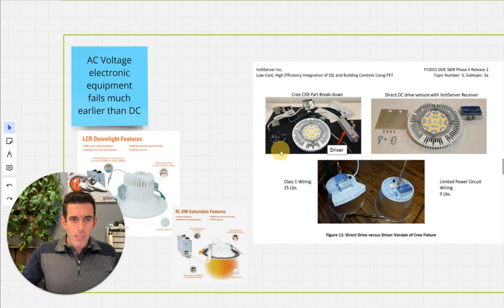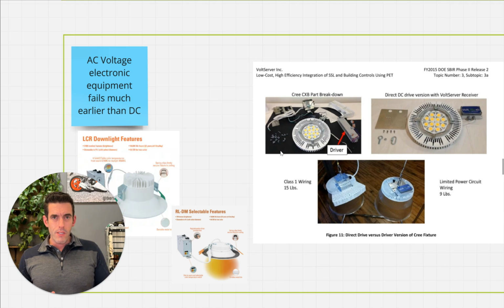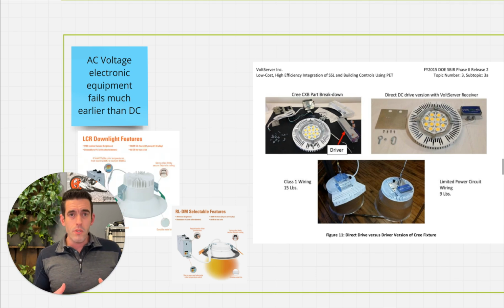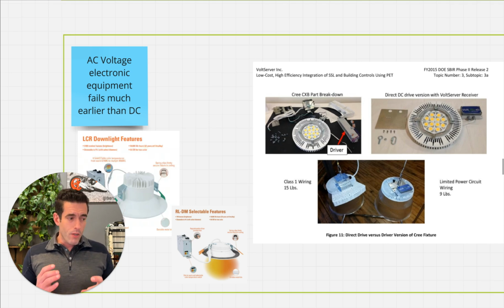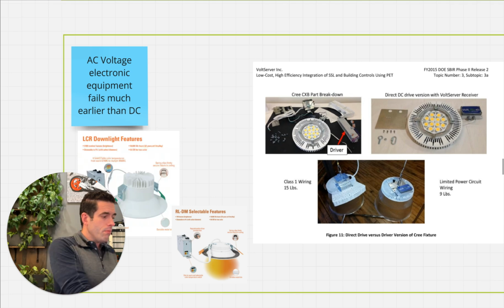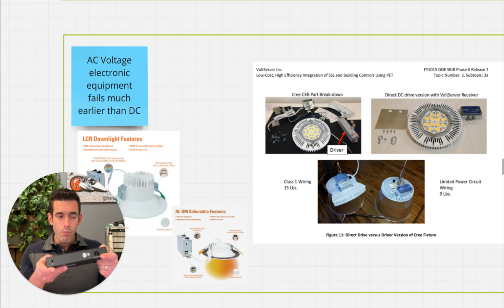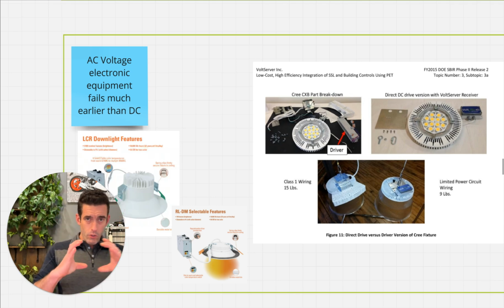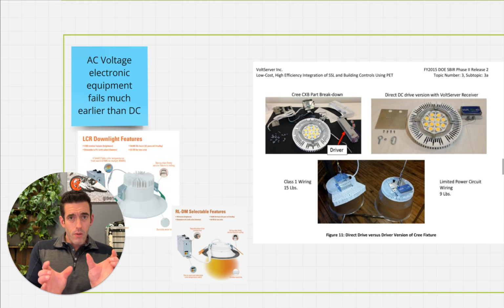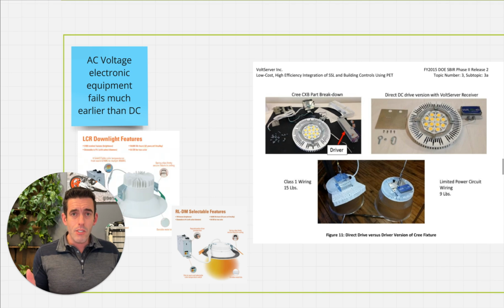The other side of it is AC voltage equipment typically fails much earlier than DC. This is not our marketing claim, this is the national labs - they've done quite a few studies on it. If you look at mean time to failure reports for equipment that can take both, some IT equipment has a power supply that takes either, and you look at, say, Cisco's mean time to failure reports, the AC voltage one is X number of hundreds of thousands of hours, and the DC one is almost always about 2.5 times as long.